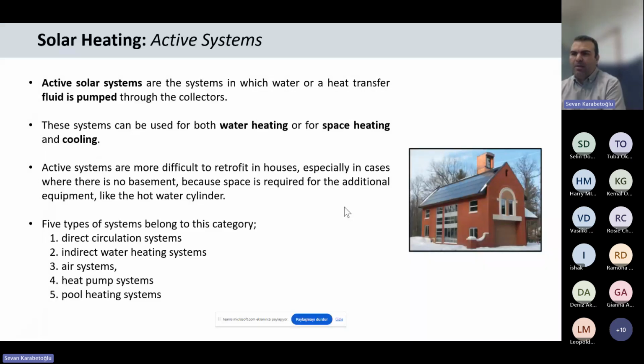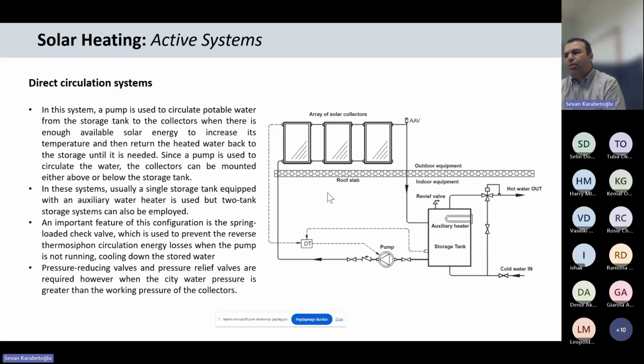Actually, five types of systems can be listed: direct circulation system, indirect water heating system, air system, heat pump, and pool heating. As I said, I will not go into the details for all of them. I just selected three. First of all, let's start with direct circulation systems. Here we have a pump to directly circulate the water itself. The storage tank will be connected with the collectors, of course. When there is enough available solar energy to increase its temperature, the heated water returns to the storage tank. In the system, a single storage tank is equipped with an auxiliary water heater, because the demand increases with usage. So there will be an additional electrical auxiliary heater. An important feature of this configuration is a check valve, because we have to prevent reverse thermosiphon circulation due to energy losses when the pump is not running.